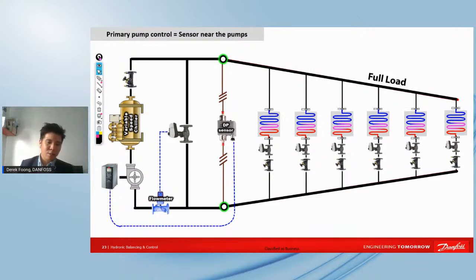But there are some sites also, a certain percentage, where you can see the differential pressure sensor across the main header right here. The differential pressure sensor consists of a high side and a low side. These are the tubings where you take feedback. It takes pressure sensing points from these two, and then it sends the signal back to the inverters, because inverters can act as controllers. Then whenever the control valve closes in the system, if pressure builds up, or before it builds up, it tells the pump to reduce the speed.